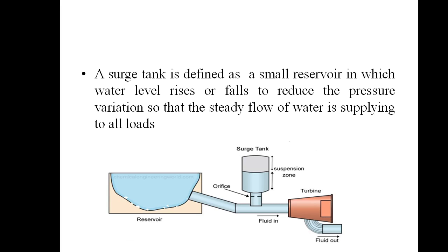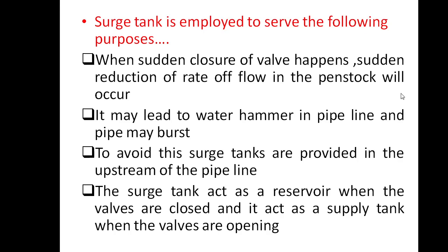Sudden reduction of rate of flow in the penstock will occur and it may lead to water hammer in the pipeline. Due to this, the pipe may burst. So to avoid this situation, surge tanks are provided in the upstream of the pipeline, and the surge tank acts as a reservoir when the valves are closed and it acts as a supply tank when the valves are opening. Okay, that is the purpose of the surge tank.